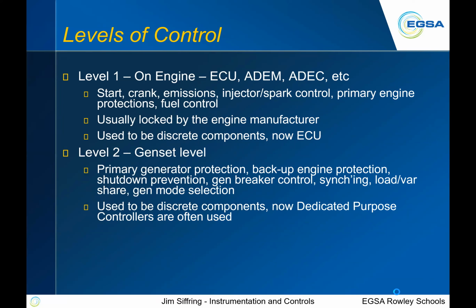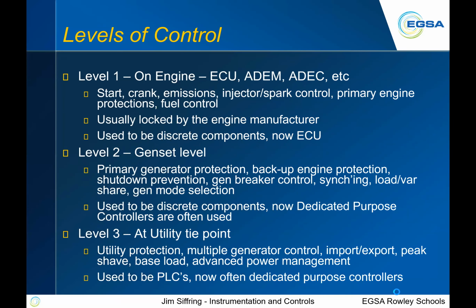Level 2 is a genset. Now we're going from the engine itself to taking in the rest of it. So the alternator, all those other things, along with the breaker control, sync devices, load share, all that kind of stuff, mode selection. And again, it used to be these discrete components, and now it's dedicated purpose controllers. And then level 3. Level 3 happens, say, if we're going to tie to utility, at the tie point. So this will be where we get all the things like utility protections, the relaying, import export power, base load, peak shaving, all that sort of thing. And again, this all used to be done by PLCs. Now it's pretty simple to get a controller to do all that stuff for us.